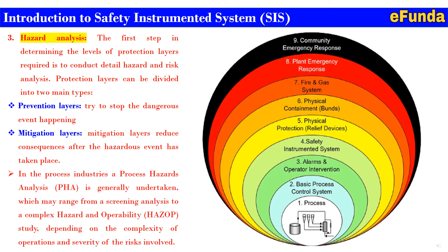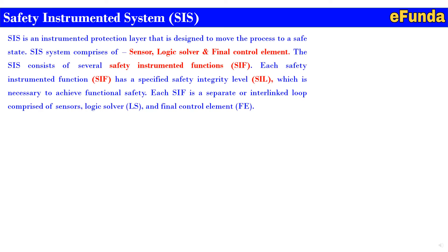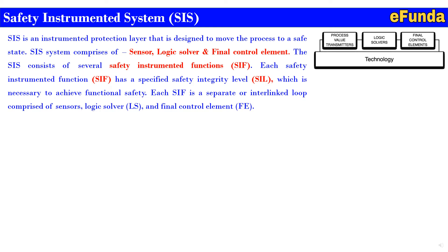In the process industry, a process hazard analysis (PHA) is generally undertaken, which may range from a screening analysis to a complex hazard and operability study (HAZOP), depending on the complexity of the operations and the severity of the risk involved. The SIS is an instrumented protection layer designed to move the process to a safe state. This system comprises a sensor, logic solver, and final control element, as shown in the block diagram.